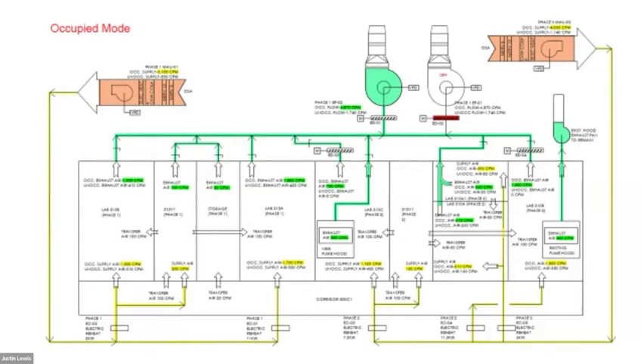There was also an independent exhaust fan feeding an existing fume hood, but that ran 100% of the time and didn't come into play with the occupancy. So again, no VAVs, no air valves, no modulation. So let's assume that the pressure cascade could be met with the occupied CFMs listed. We get everything balanced, set in place, locked, and everything's working.